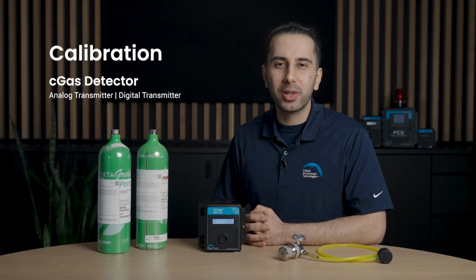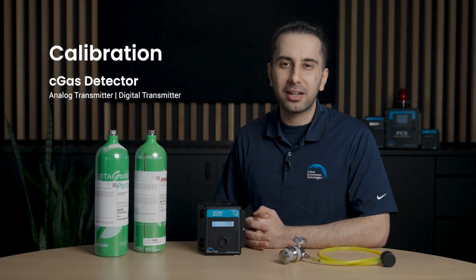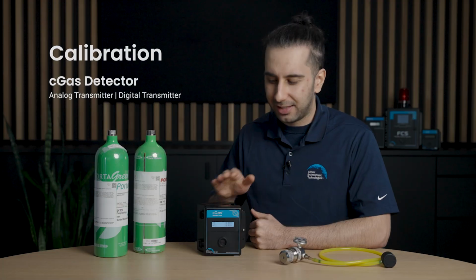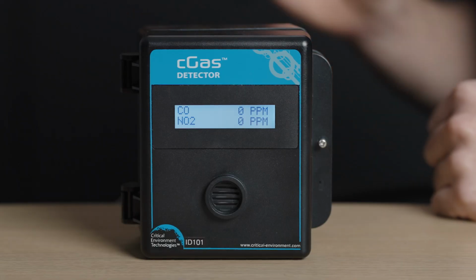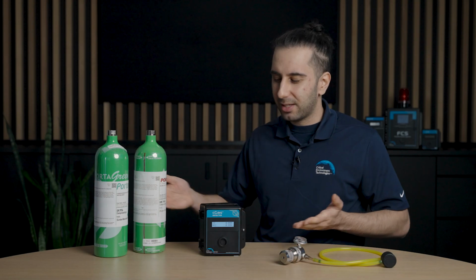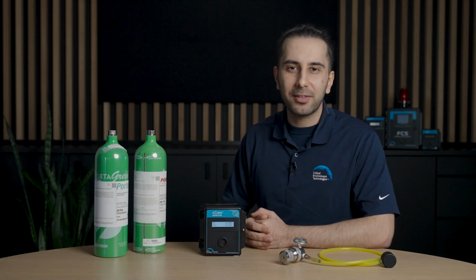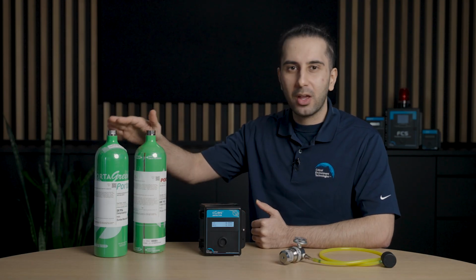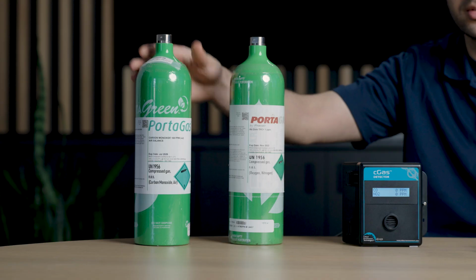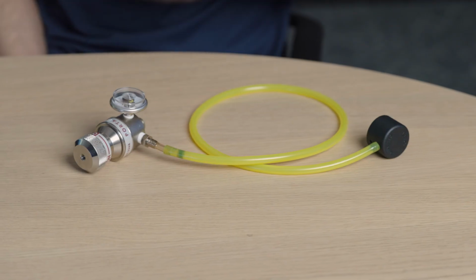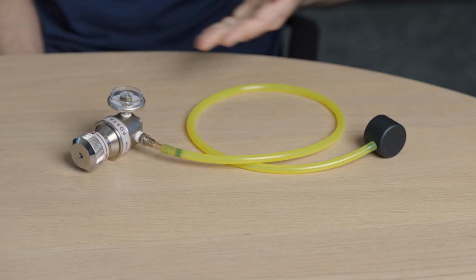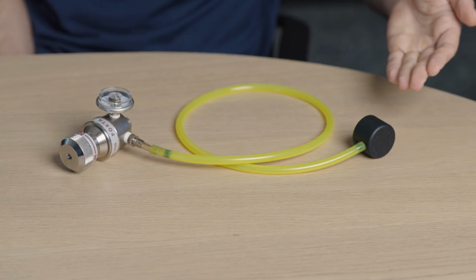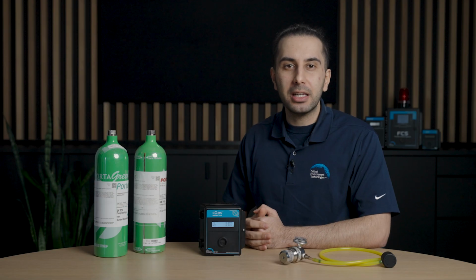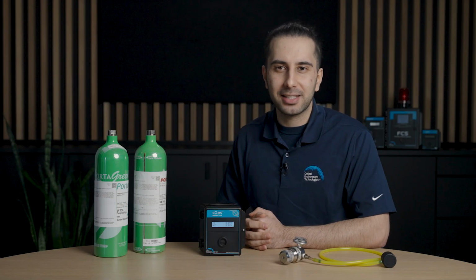In this lesson, we will cover the calibration process of an internal sensor on a cGas detector. To perform a calibration, you will need these pieces of equipment. Here, we have calibration gas cylinders, one for zero gas and one for span gas, a regulator, tubing, and a calibration clip.